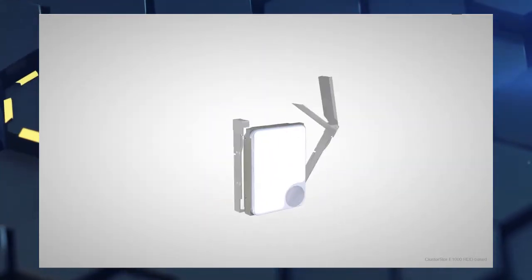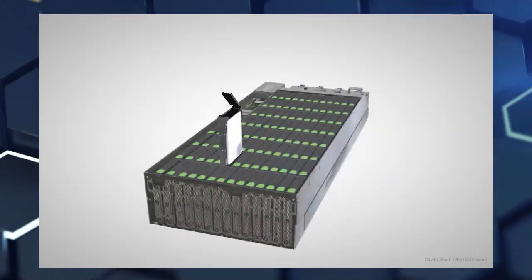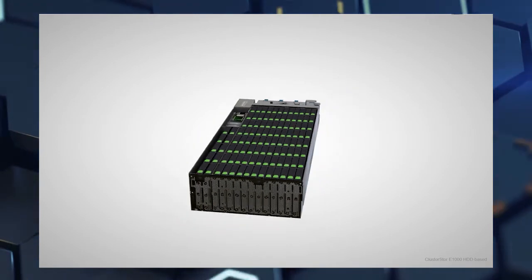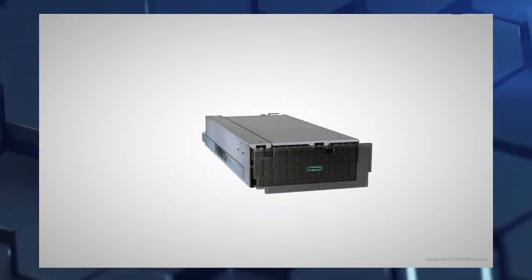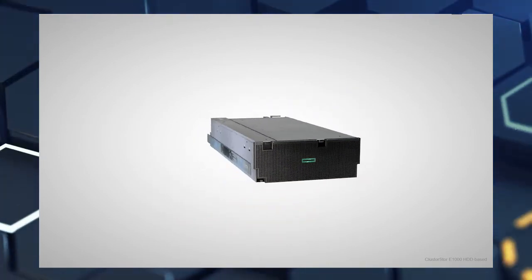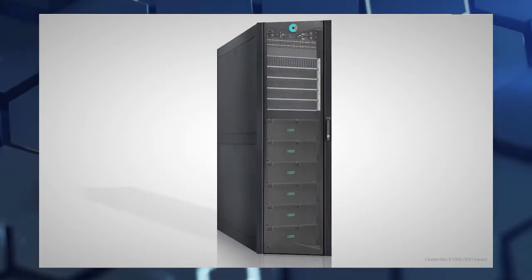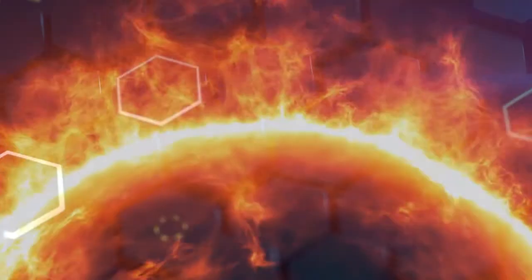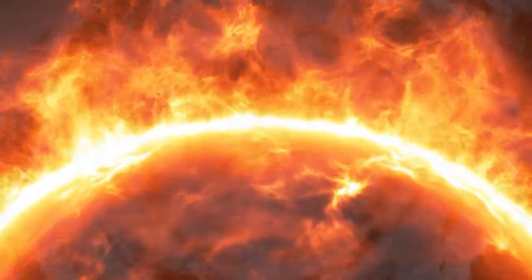Supporting the Frontier, there is a storage subsystem with 700 petabytes of capacity and 75 terabytes of maximum throughput, developed based on the Cray ClusterStor E1000 storage system. At a regular working performance, Frontier generates 30 megawatts of heat, which is then absorbed by 22,712 liters of water circulated by four 350 horsepower water pumps.